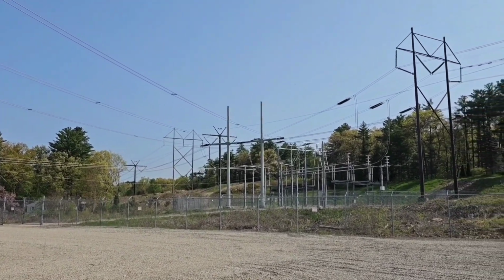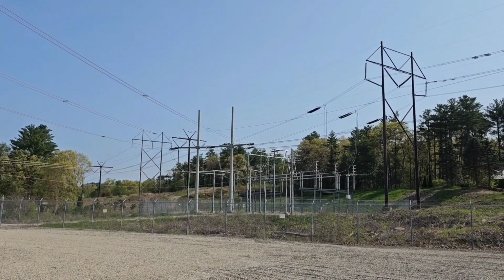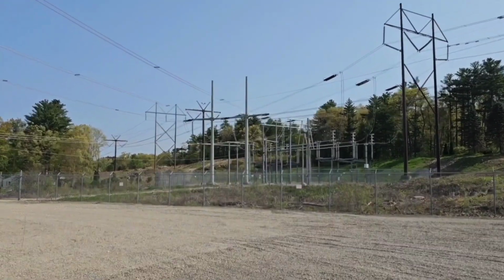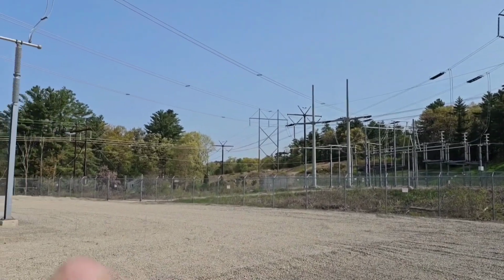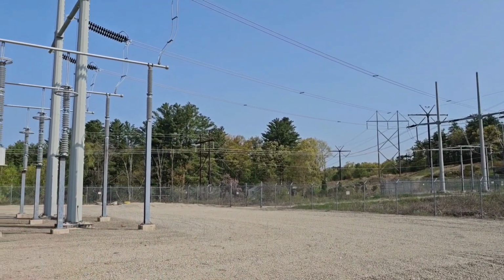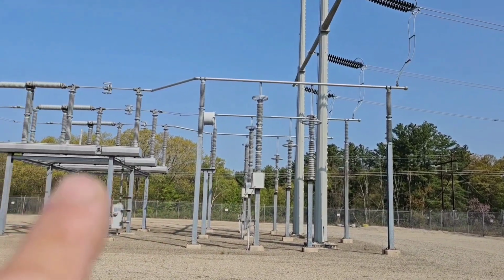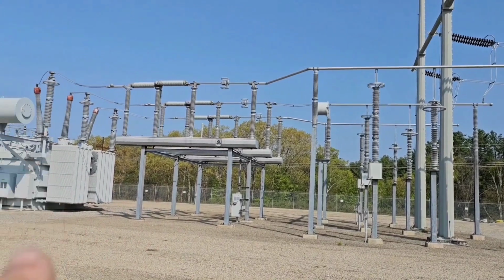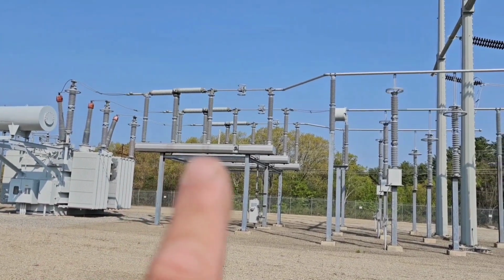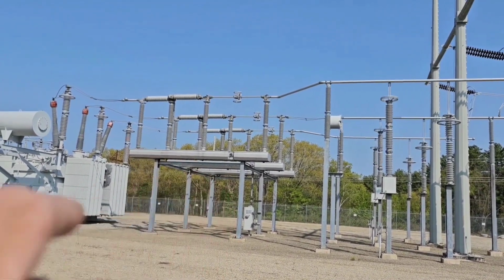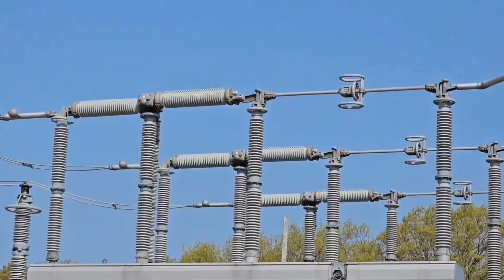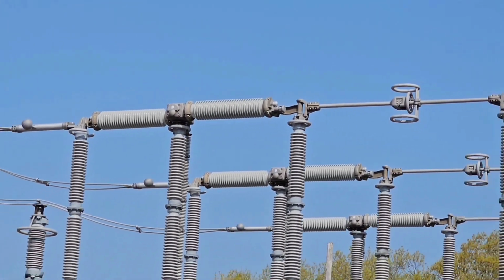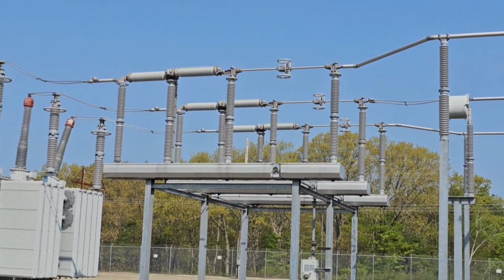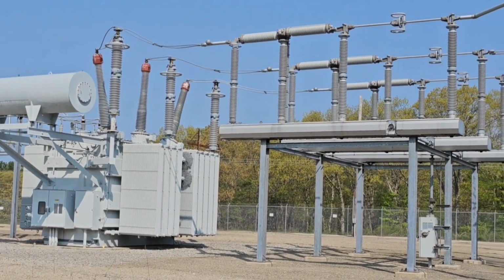These high voltage lines bring the power from a further distance, and then they come to one of these switch yards that you see here, and they can pick whichever line they want to come into the substation. Then that line feeds into the substation through this switch and into the transformer. This switch has an insulating gas inside these bottles, which is how the arc is broken if they need to take this transformer out of service.